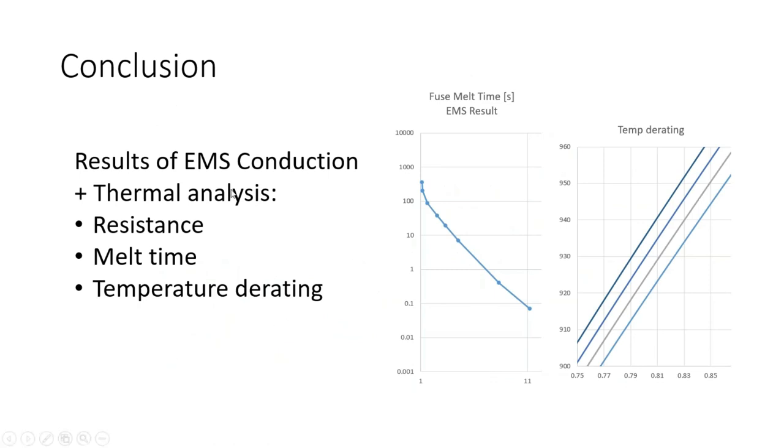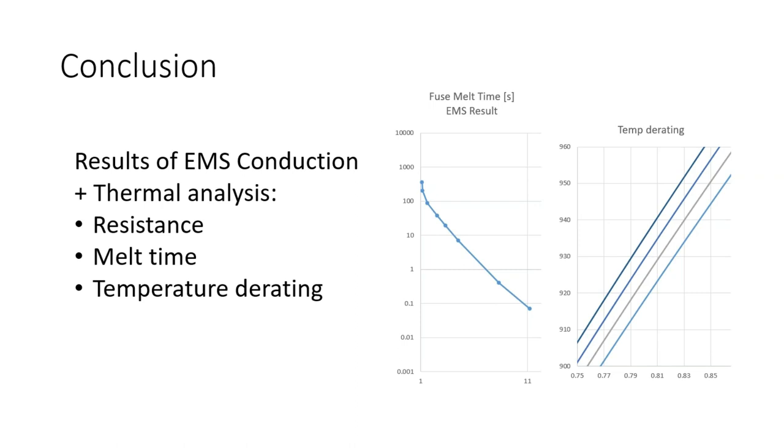As we have seen, results obtained from EMS electric conduction study together with thermal analysis allowed us to compute some of the important parameters for fuse design. We have been able to compute resistance of the fuse, melt time for different current values as well as melt time for different ambient temperatures. These are the results fuse designers absolutely need and EMS is definitely capable of providing those results and being a competitive fuse design software.